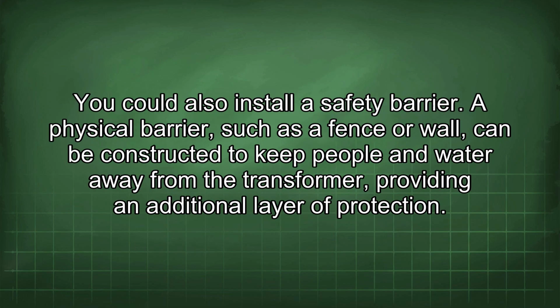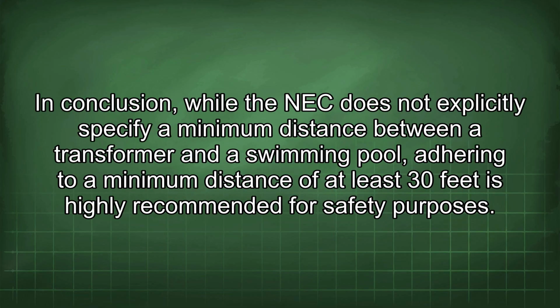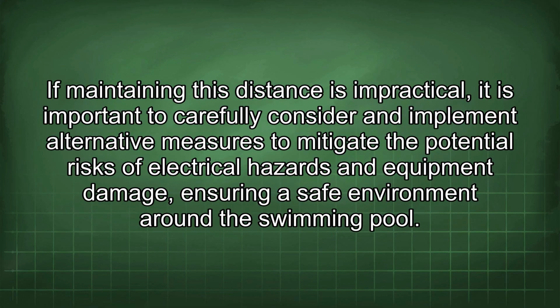You could also install a safety barrier. A physical barrier, such as a fence or wall, can be constructed to keep people and water away from the transformer, providing an additional layer of protection. In conclusion, while the NEC does not explicitly specify a minimum distance between a transformer and a swimming pool, adhering to a minimum distance of at least 30 feet is highly recommended for safety purposes. If maintaining this distance is impractical, it is important to carefully consider and implement alternative measures to mitigate the potential risks of electrical hazards and equipment damage, ensuring a safe environment around the swimming pool.